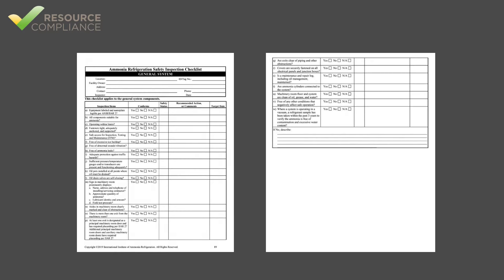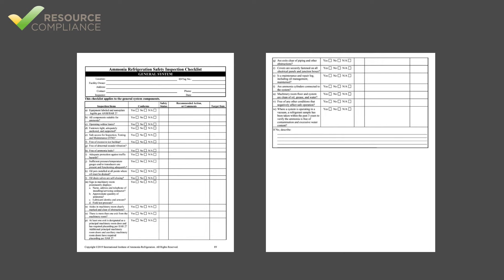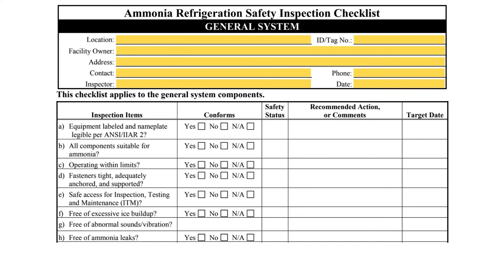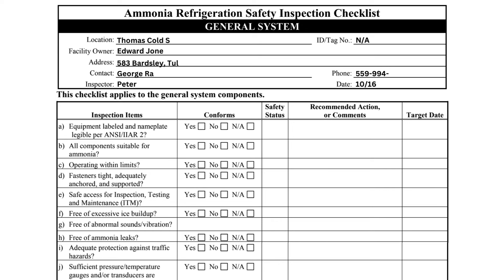The simplest part of completing the general inspection checklist is filling out the contact information. Each IIAR 6 checklist requires the inspector to indicate the location, owner, and physical address of the system. The contact's name and phone number should be the facility representative responsible for ensuring the inspection is completed. Additionally, the inspector must write his or her own name and the date of the inspection. The ID or tag number belongs in the upper right corner. Refrigeration systems are not always given a unique ID or tag number, so NA is often indicated here.